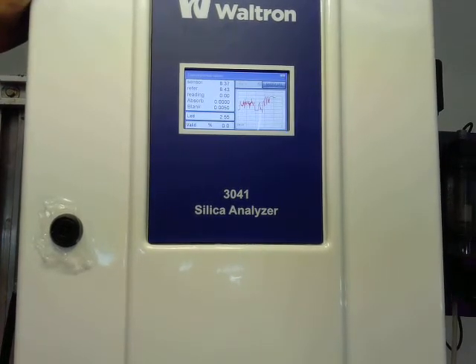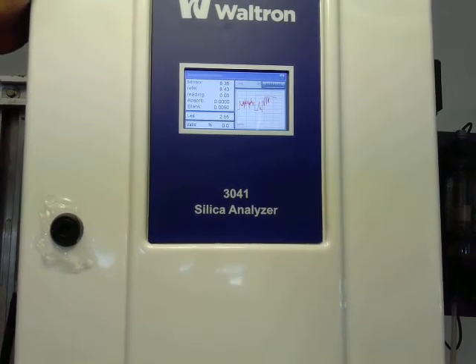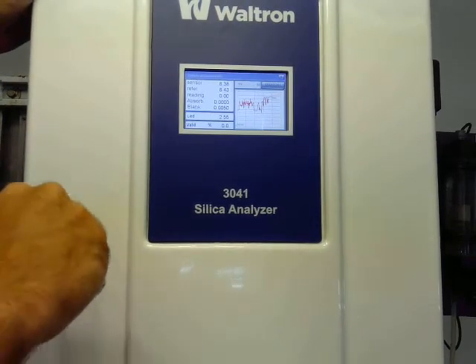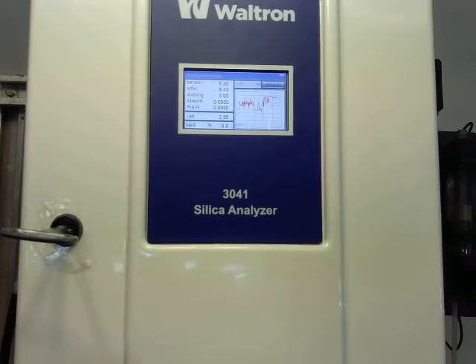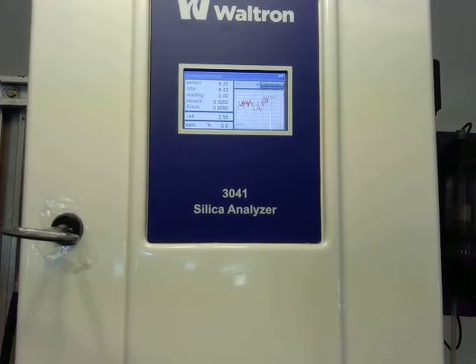And again, this number is what becomes the reference and the reading numbers when the analyzer knows that it's at the right time to take those numbers. So the exact number of what the sensor says or the exact reference number isn't necessarily as critical as the difference between the reference and the reading numbers for each measured cycle. So right now we've got a minute or two of mix time before it'll actually add reagent 2, and then we'll have another mix for about a minute, and then we'll see the reference number update with whatever the sensor value is reading at that particular time.